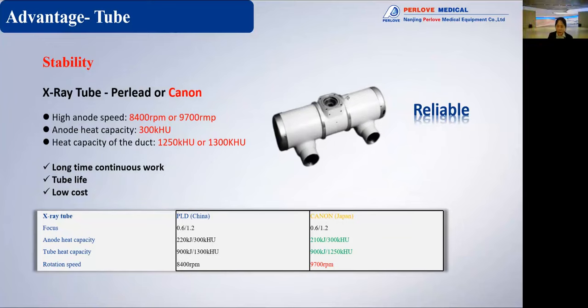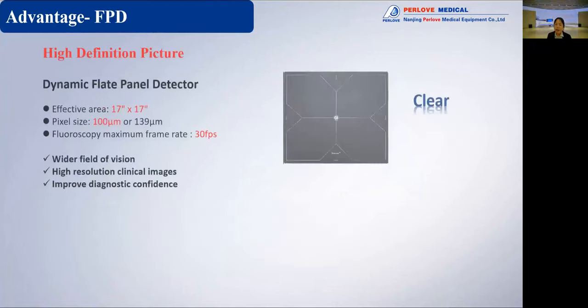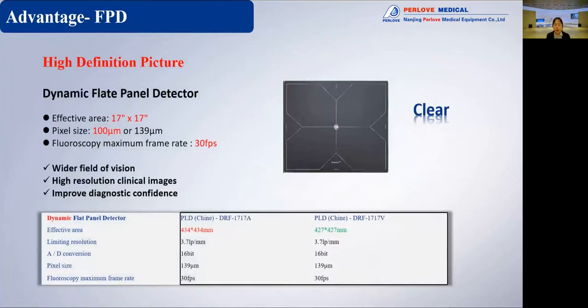Next, I would like to use 'clear' to describe this machine. Why? This model uses the dynamic flat panel detector to achieve radiography and also motion observation. I will tell you the difference between the dynamic flat panel detector and the static flat panel detector. Why we choose dynamic flat panel detector?